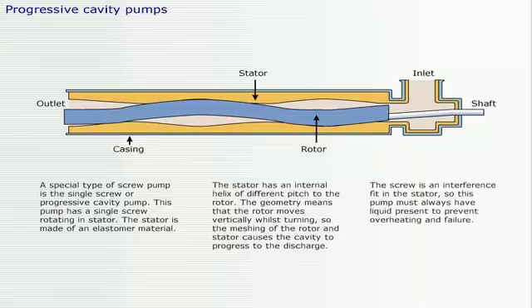The screw is an interference fit in the stator, so this pump must always have liquid present to prevent overheating and failure.